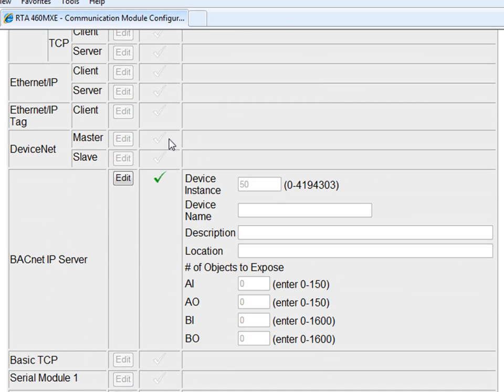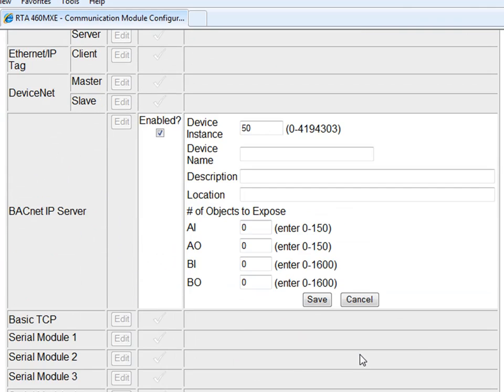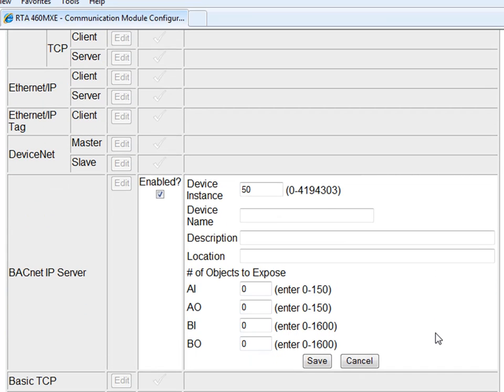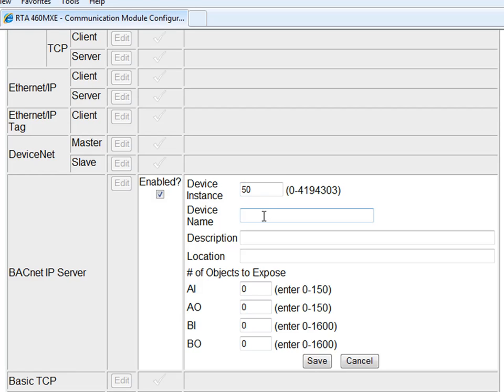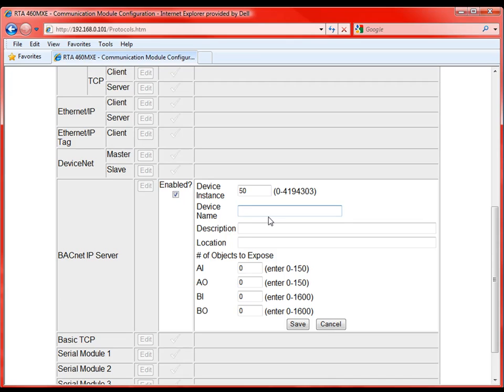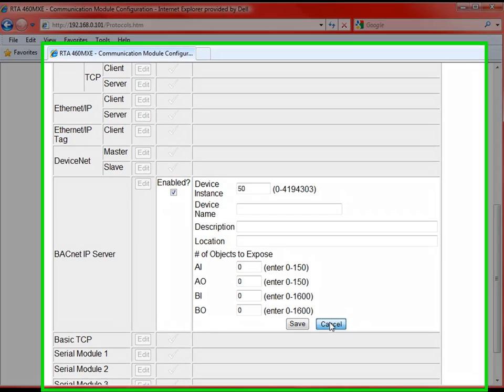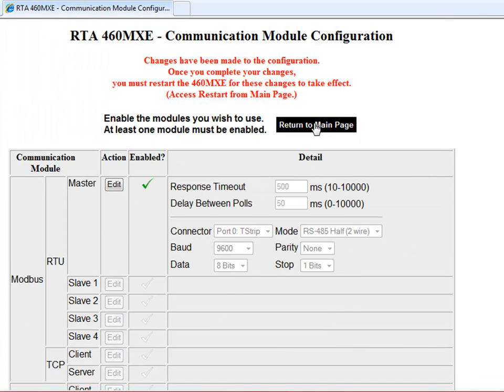If we then go down to the BACnet IP server, here we're able to define what our device and the data it presents will look like to the BACnet IP client. The device instance is a lot like a slave address on the Modbus side. So we're going to be device instance 50, so when the BACnet client goes to pull device instance 50, they'll see us. Here we can enter another name, a description, and location, and this would be the data that would be put out on BACnet IP. Down here you'll see number of objects exposed. Because this is the 460MXE, this is defined in the template file, so we don't have to expose any of the analog or binary inputs or outputs.